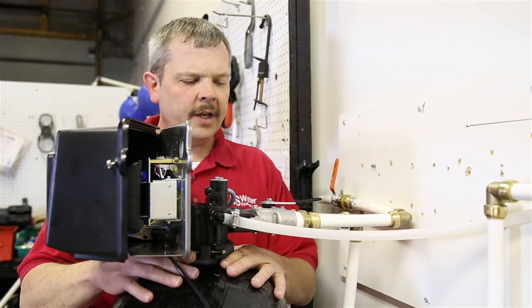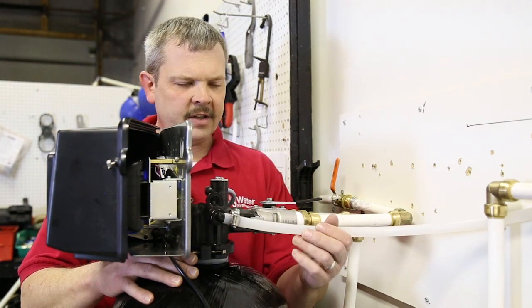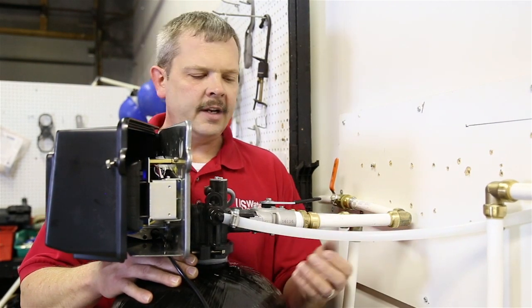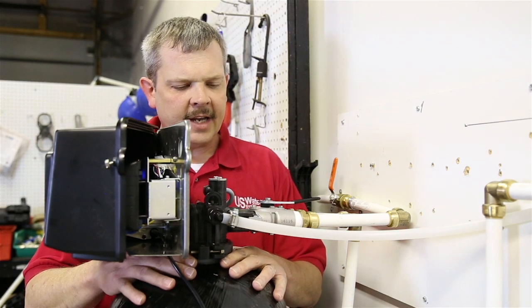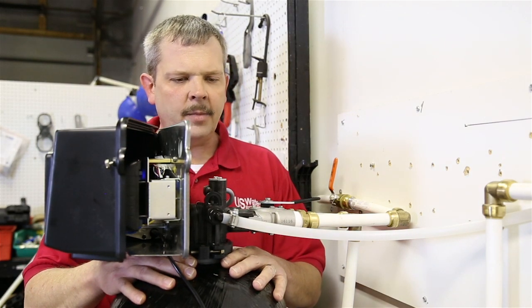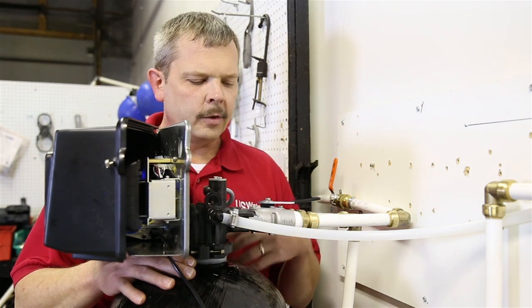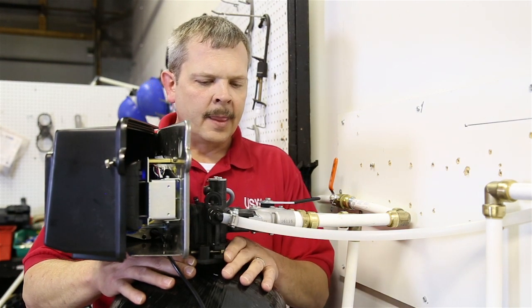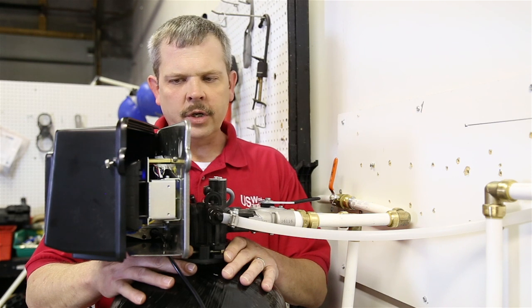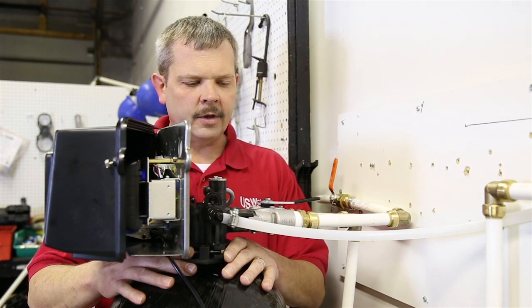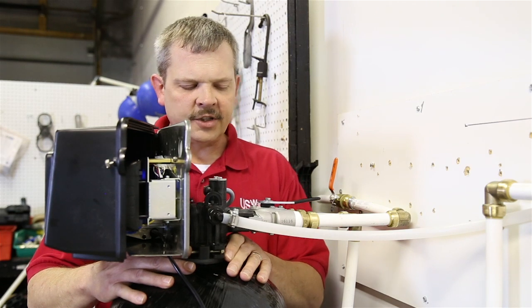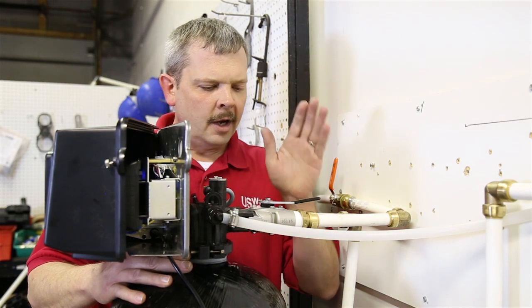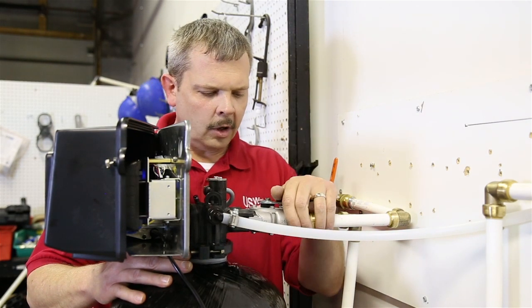As this fills the tank with water, eventually water will come out and you'll see water go through your drain line here. But you want to go slow enough that you don't get a loud knock in here. If you hear a real loud knocking noise, you're putting water in so fast that the air is having trouble to escape. So during this 14 minute period, you're going to slowly move it a little bit more and a little bit more until we have this fully opened in the service position and the tank is full and discharging. You can feel the side of the tank too and feel the temperature as it starts to get colder. You can kind of tell where the water level is as it fills.